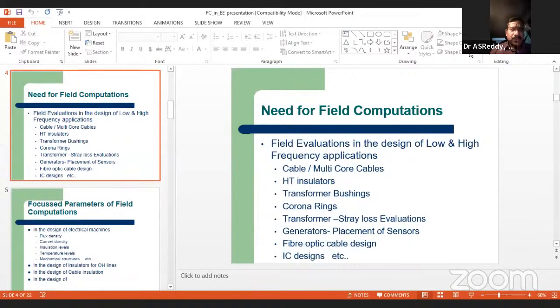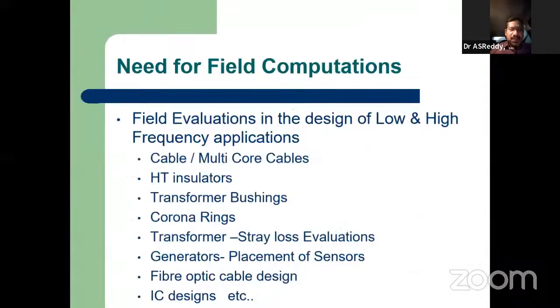Yes sir, here are the examples. In design of cable, especially multi-core cables, and in designing some HT insulators and bushings, the field distribution really affects the design of the insulator. So this field computation method helps us to exactly design the shape, size, and type of material of the insulator.